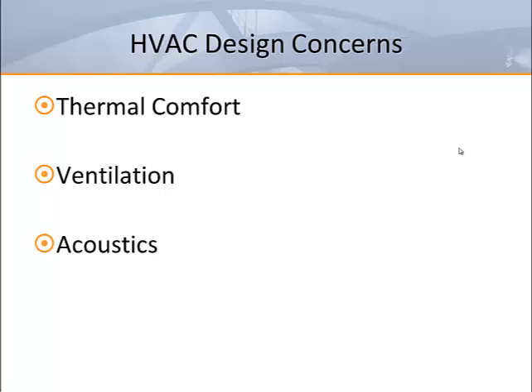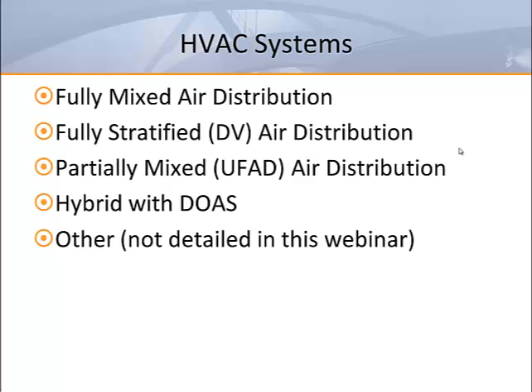Our focus for today's webinar will be on designs that address the thermal comfort requirements, the ventilation requirements, and the acoustic concerns for schools. This webinar will cover the thermal comfort, ventilation, and acoustic design elements required for a traditional fully mixed air distribution system where comfort air is supplied through grills and diffusers mounted in the ceiling or areas outside the occupied zone. Also, fully stratified systems such as thermal displacement ventilation, and partially mixed air distribution, such as underfloor air distribution systems.